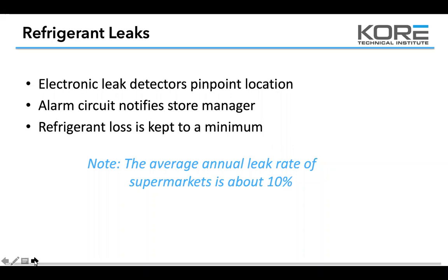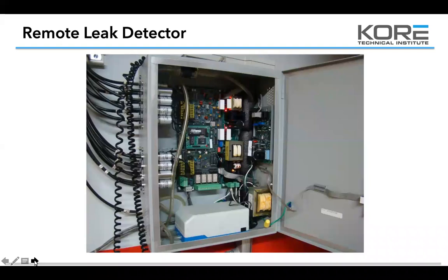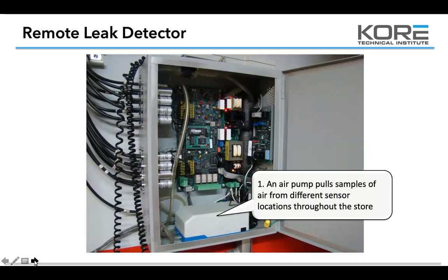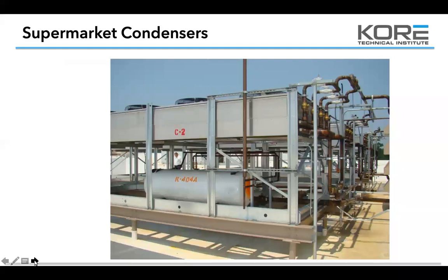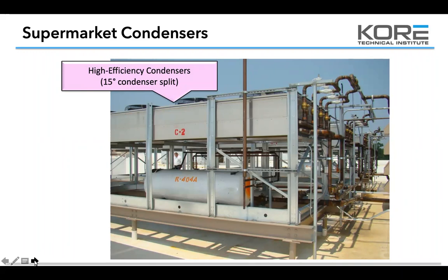The average annual leak rate of supermarkets is about 10%, which is quite a bit. Your average supermarket holds anywhere from 600 to 1,100 pounds of refrigerant per rack. This is an infrared leak detection system — an IRLDS. You've got your air pump that pumps air through to take a sample, and your microprocessor that takes the air sample and checks for parts per million of refrigerant. In this application the receiver is actually on the roof with the condenser — you might see that from time to time. Up to 1,500-pound capacity — that's a big boy.